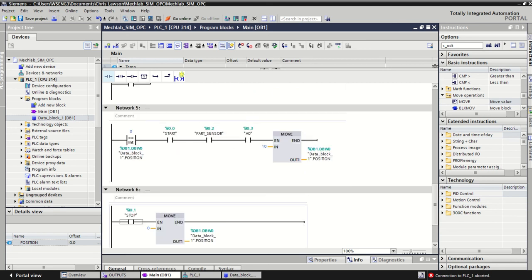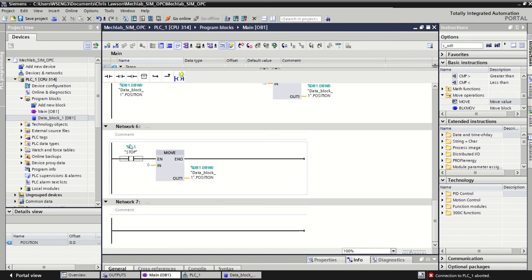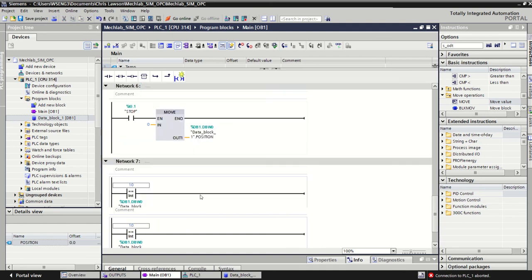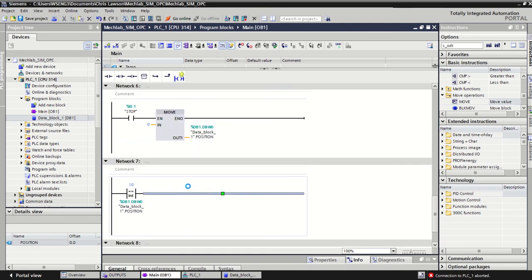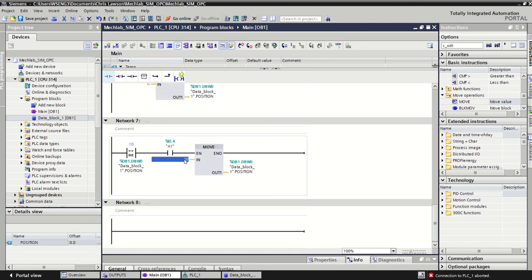Right, brilliant. So that's the start, right? So imagine everything is at rest, we've put a part in, doesn't matter what it is, we've pressed start and the cylinder pushes it forward. So we said the motor has come on, it's latched on, and the cylinder has moved forward. So I need the cylinder then to come back automatically. So basically I want to make sure it gets a full extension, so it goes right up, gets its max proximity sensor, and then it automatically returns. So what I want to do is basically, we've gone into step 10. So we're in step 10, and then once we check that we get to A fully extended, which is told by my A1 sensor, then I want to go ahead and move into step 20.